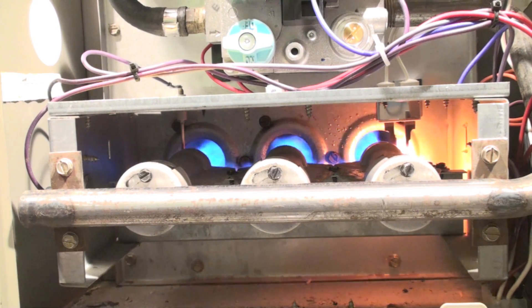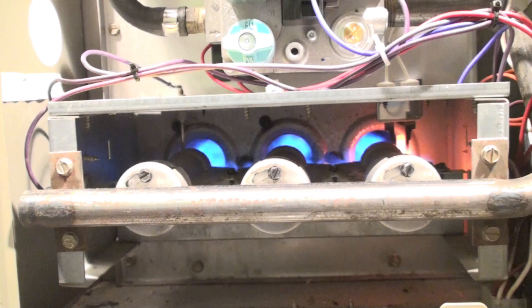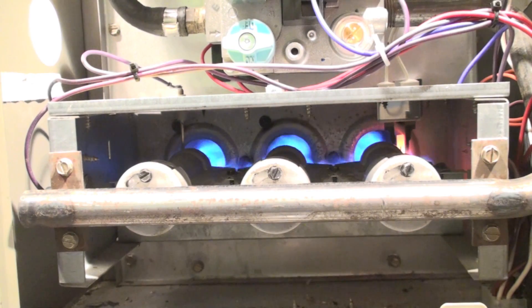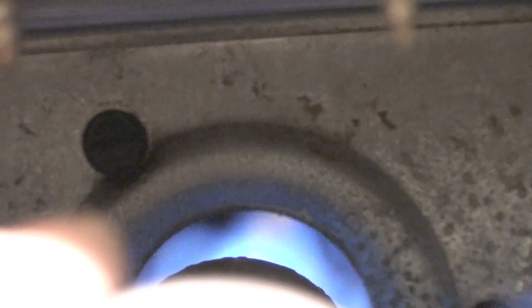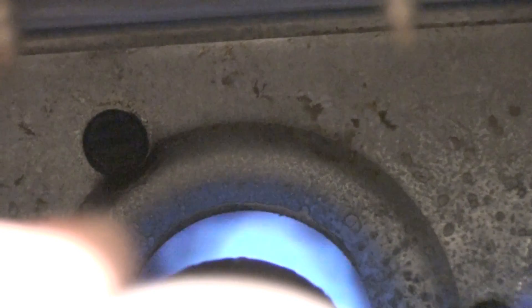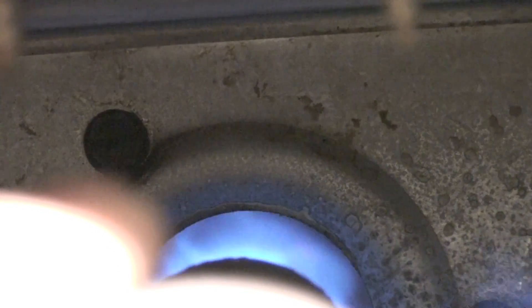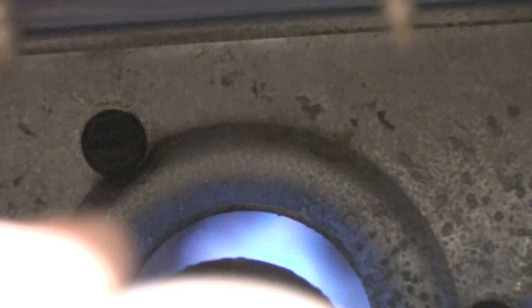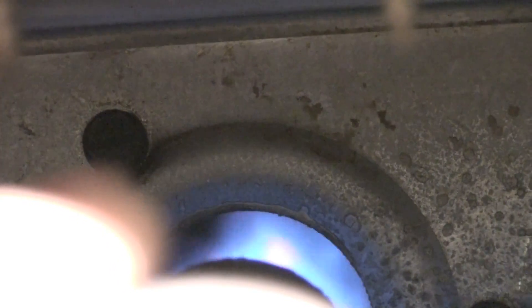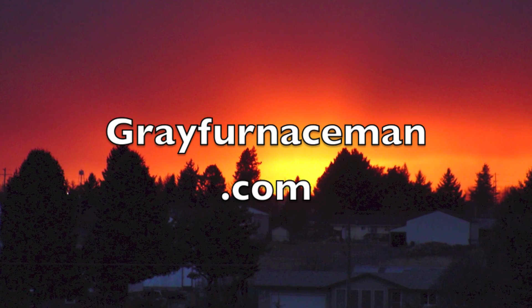Okay, pretty hard to tell on this one. Looking in there, let me see if I can get you closer. Okay, you can see the yellow there. When I turn that little slide, it kind of turns blue. It's a little hard to tell, but it is actually working, and that's adjusting the burners to get the yellow tips off.